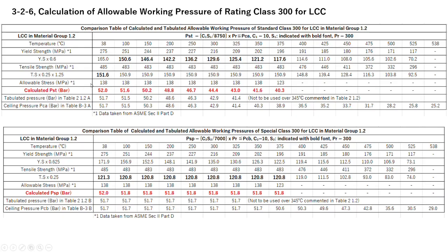So allowable stress value indicated, so temperature limitation 375 in the ASME section 2 part D. So LCC casting material to be used for pressure retaining material up to 375 degrees Celsius. So 400 degrees Celsius cannot be used for LCC casting.